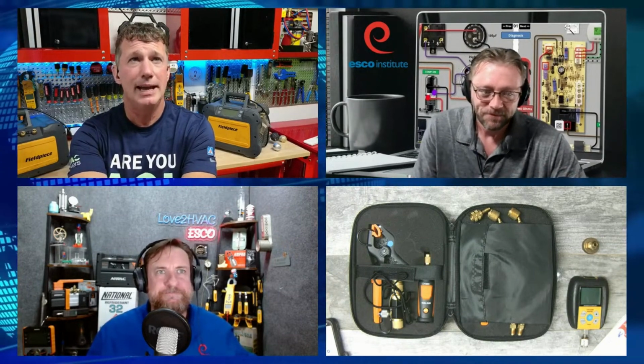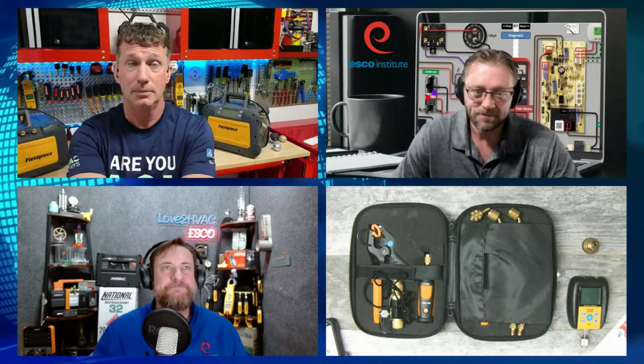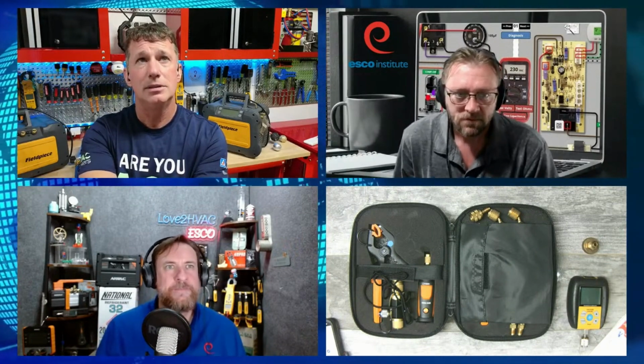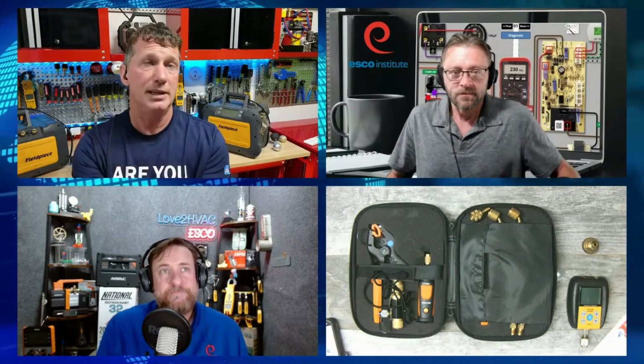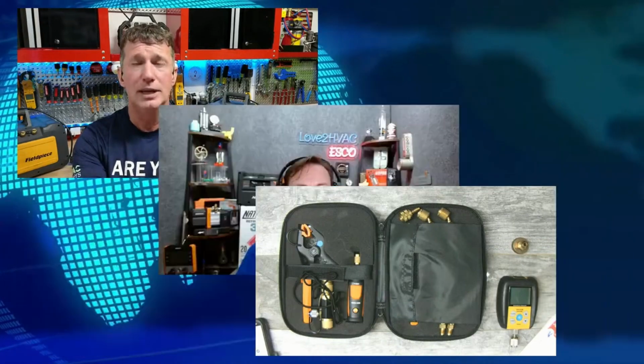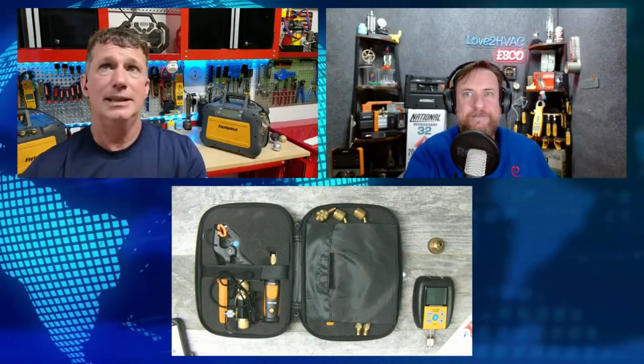Well, think about a vacuum pump that uses a PSC motor. Traditionally, we used a mechanical switch for that PSC motor, and it would not be considered A2L compatible. What if I took that mechanical switch and used a concealed solid state control for that? Could I use a PSC motor? The answer is actually yes. One of the Navac pumps, they have an entry line A2L compatible pump, and that's exactly the process they relooked at. I've also seen JB doing the exact same thing. Still utilizing the same PSC motor, just changing the controls to make sure that the controls cannot provide any type of ignition in that environment.